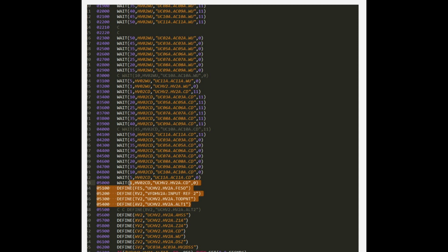Programs that contain fewer lines will be executed faster than longer programs. For example, a field panel contains two programs, one with 10 lines and the other with 50 lines. The shorter program will be executed 5 times before the longer program is executed once.